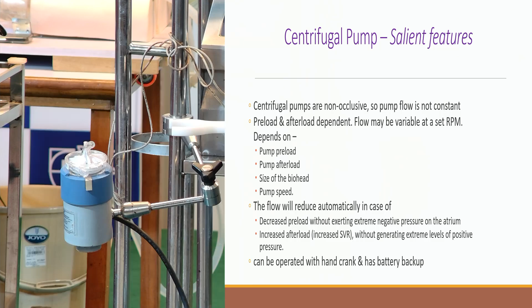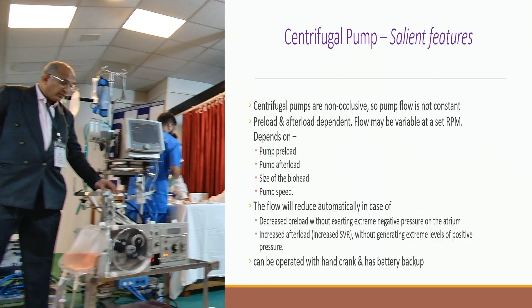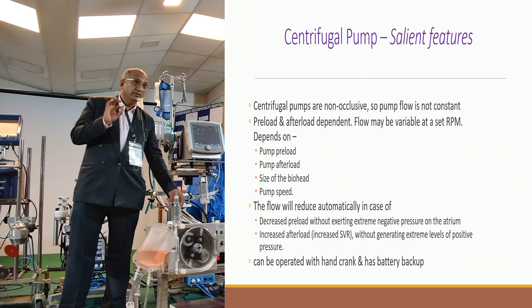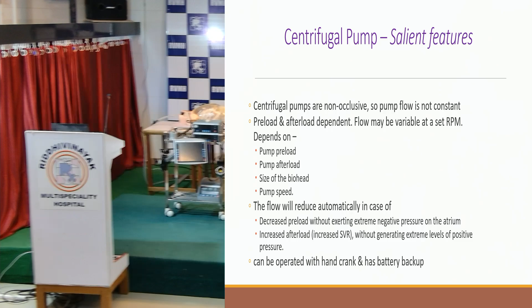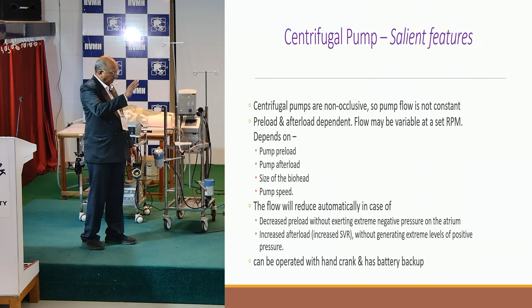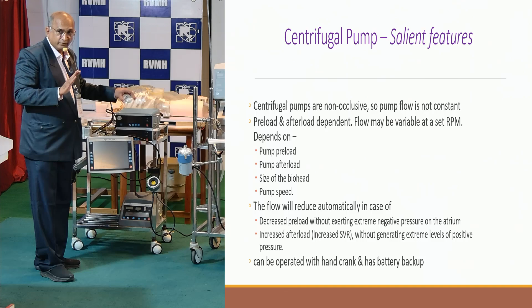So here, in case of Medtronic, with 2000 RPM you might get a flow of around 4 liters. But here, because the pump size is so small, with 2000 RPM the flow will not be even 500 ml. So each machine with the RPM, the flow will differ. You have to keep that in mind. Medtronic, Sorin, more or less the same RPM. Mackay and Centrimec, more or less the size of the pump, there's not a big difference. But Meadows is the smallest size pump, and that's why the requirement of RPM is very high in case of Meadows.